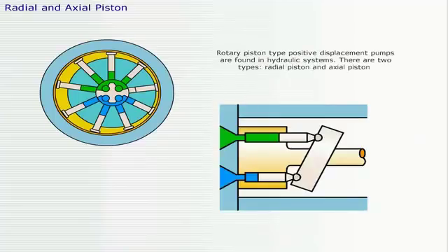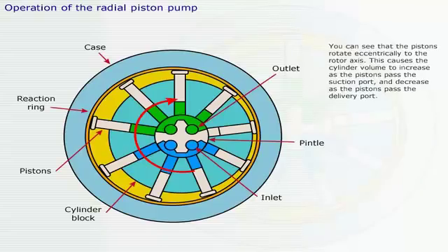Rotary piston type positive displacement pumps are found in hydraulic systems. There are two types, radial piston and axial piston. You can see that the pistons rotate eccentrically to the rotor axis. This causes the cylinder volume to increase as the pistons pass the suction port and decrease as the pistons pass the delivery port.